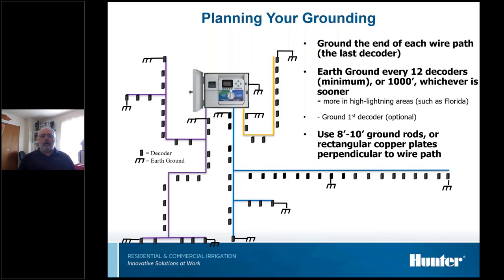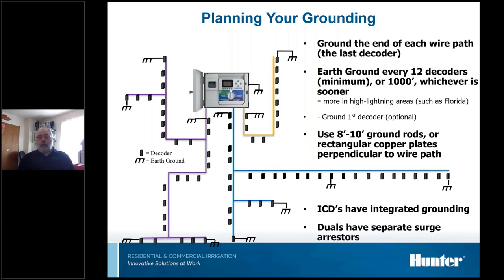Then it's the same thing, 8 or 10 foot rods or the plates perpendicular to the wire path at each one of those locations. This is a note: our ICD decoders, which is what ACC and ACC2 controllers use, have integrated grounding. It's built right into every decoder. You just ground every 12th decoder or 1,000 feet. It's not a separate device. The dual or I-Core system does use a separate surge arrestor.